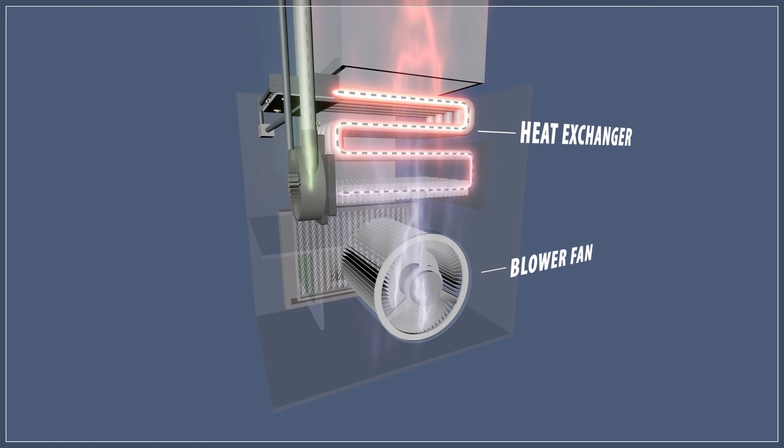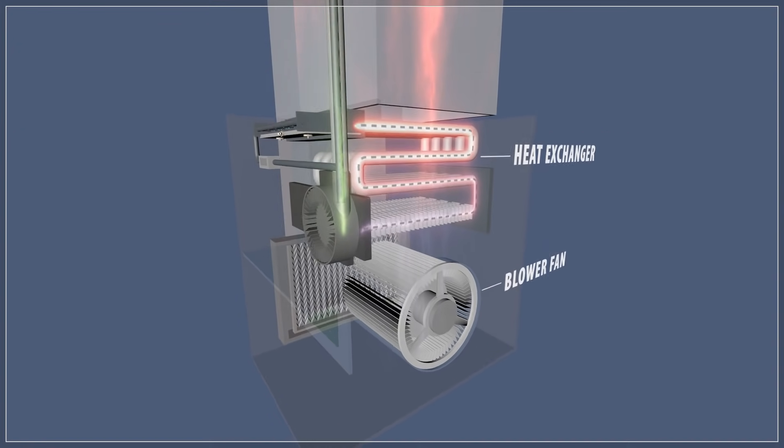If the blower fan continues to run or if the blower fan cycles on and off, then the limit switch might be faulty.